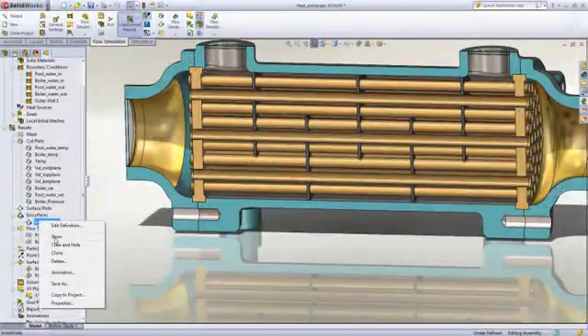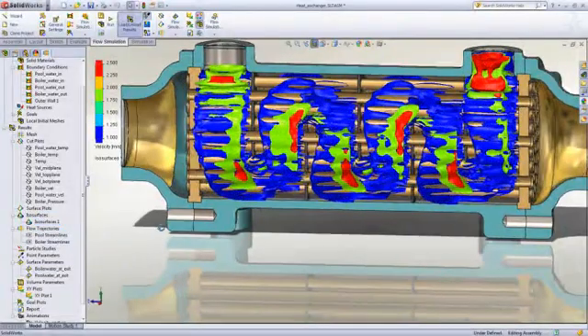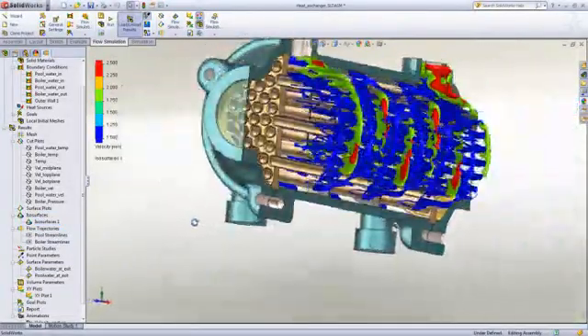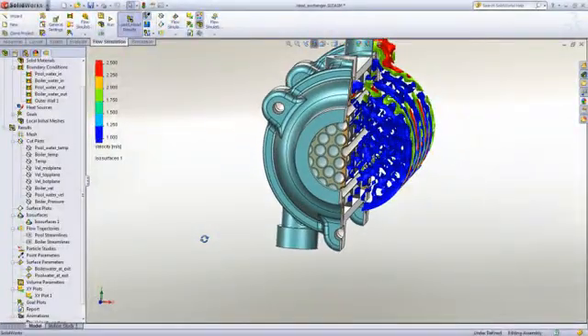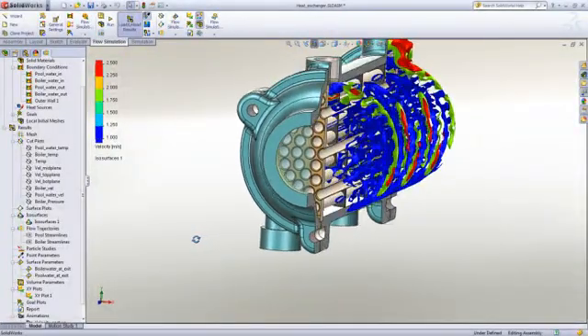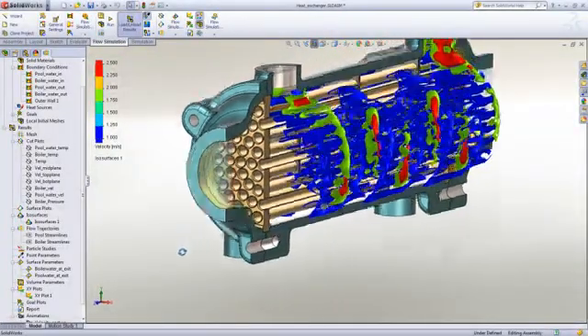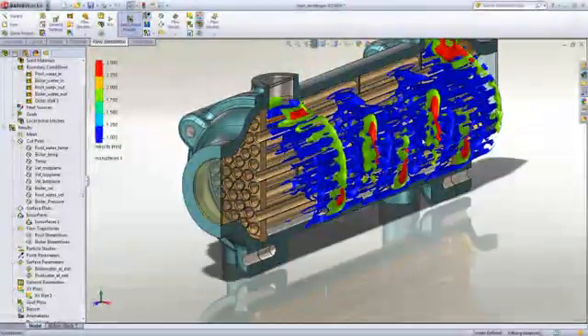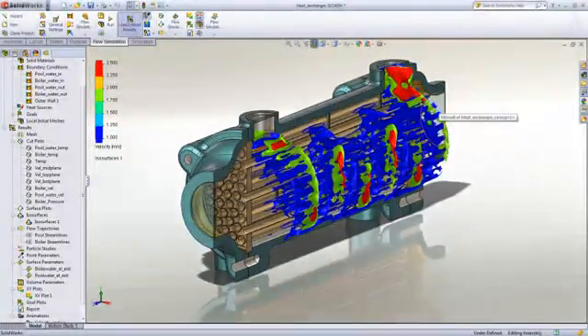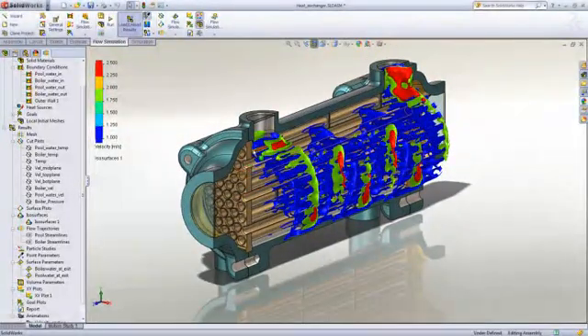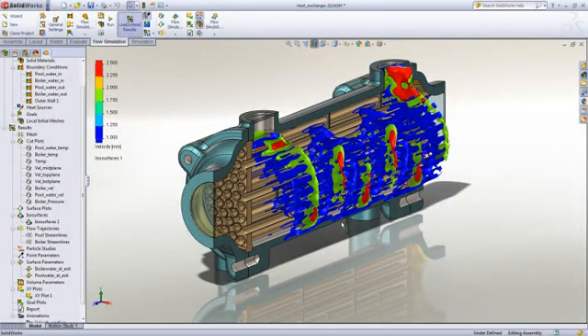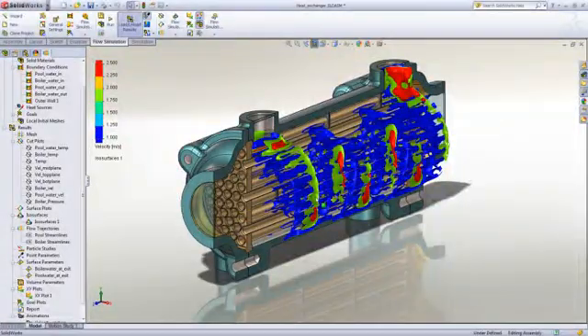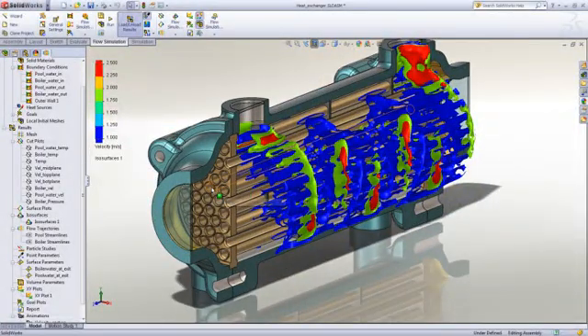ISO surfaces can help us to identify areas of concern or interest. In this instance we are looking for where the maximum flow velocity occurs. It appears that the peak flow is near the outer wall of the container suggesting that the density of the pipes is restricting much of the flow from the center of the container. This could make it worth investigating adjusting the number and spacing of the pipes to get a more efficient heat transfer.